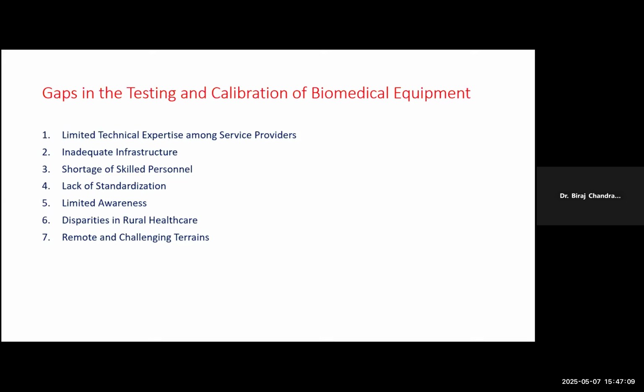Then disparities in rural healthcare. In rural healthcare, we usually observe there is no expertise, or there is no workshop. In these cases, we have observed with the implementation of the NQAS program that almost all districts have a combined system for all PHC, CHC, even the sub-centers. Equipment like BP apparatus and glucometers are taken to the districts, where there is a common facility, and from there they are doing the calibration. Remote and challenging terrains can also be addressed with a common program at the district level, so that from the sub-center level, the Ayushman Arogya Mandir, then the CHC, or the DMHO office, it can be done.